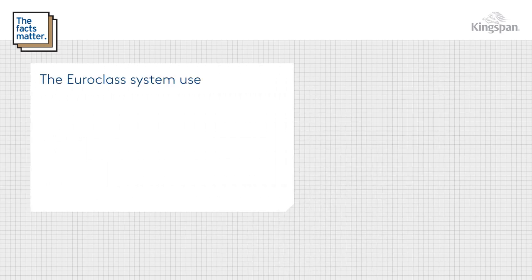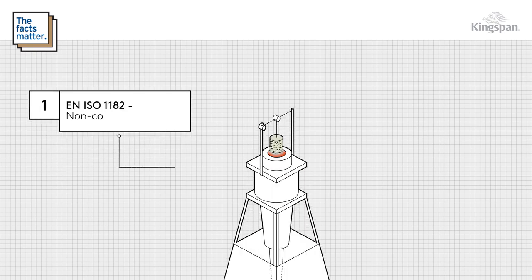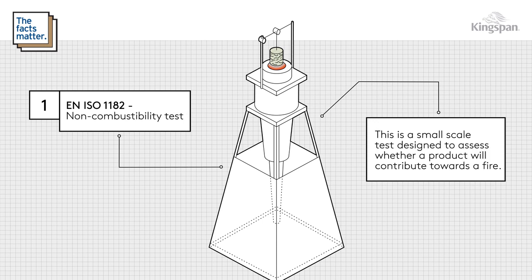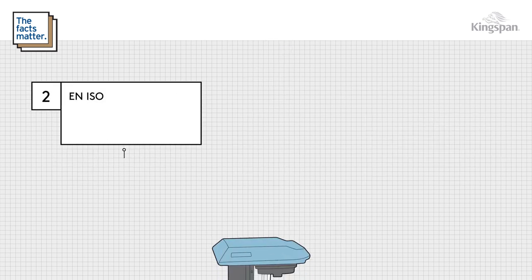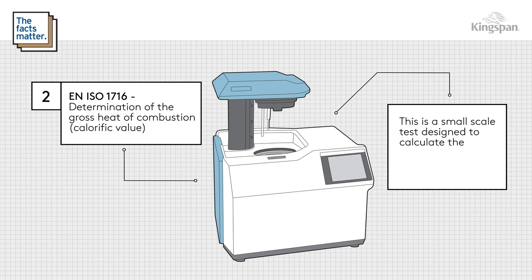The Euroclass system uses four tests. EN ISO 1182, the non-combustibility test — a small scale test designed to assess whether a product will contribute towards a fire. EN ISO 1716, determination of the gross heat of combustion, calorific value — a small scale test designed to calculate the total heat release of a specimen when burned completely.